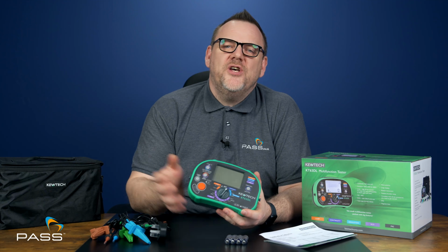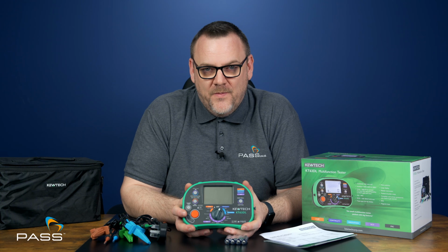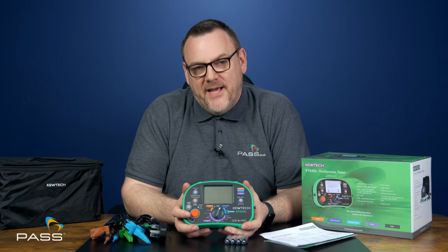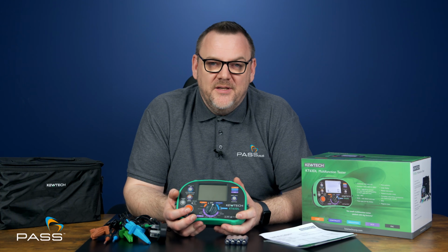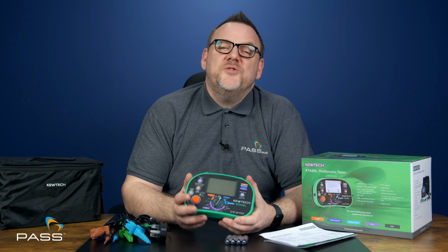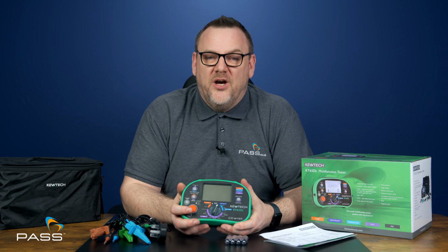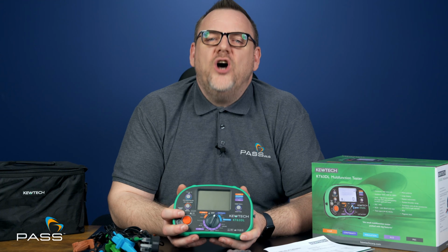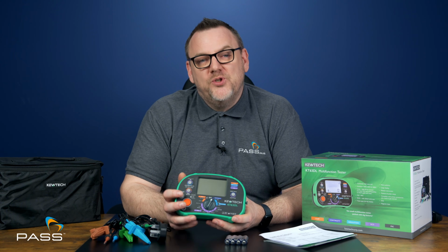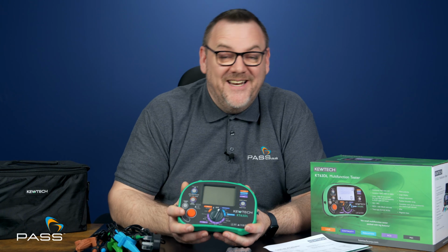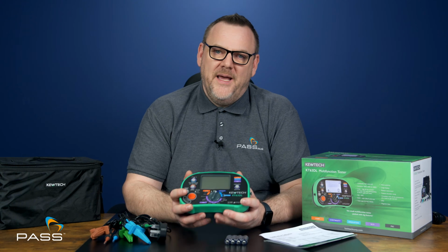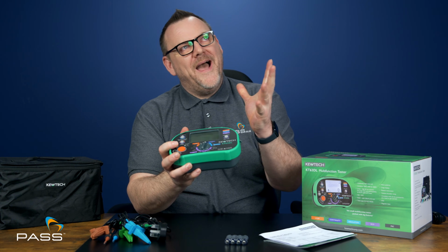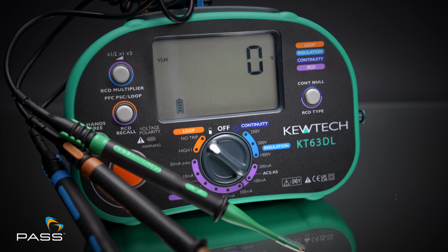Continuity testing. Open circuit voltage between 4 volt and 10 volt, with short circuit current over 200 milliamps. Also, as previously mentioned, insulation tests that offer 250, 500 and 1000 volt options. Loop impedance. This measures between 0.00 and 500 ohms with impressive accuracy. RCD testing, rated for tripping voltages between 195 volts and 253 volts AC, with ramp testing in 3 milliamp increments. It's basically all the power and precision you need for everyday testing.